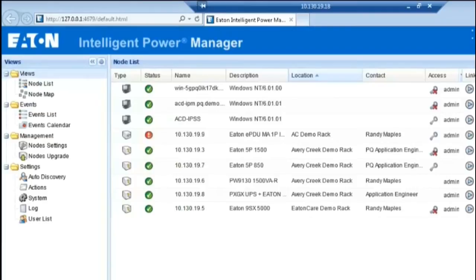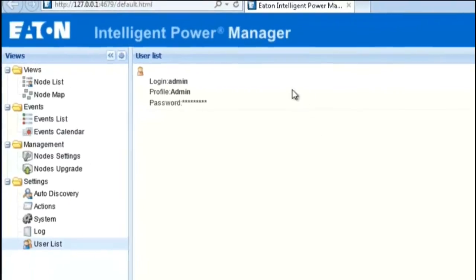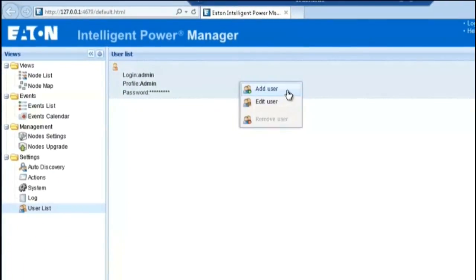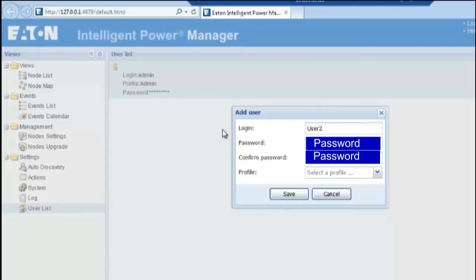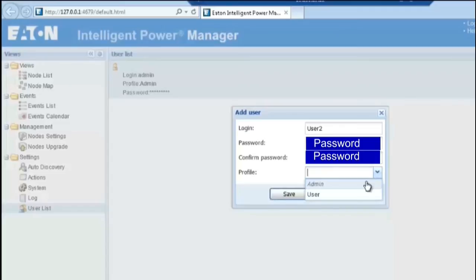Users can also be added and granted either an administrative or basic level of permissions. First, locate the Views column on the left-hand side of the interface. Next, locate the Settings folder. Then, locate the User List option. Highlight the Admin user profile found on the center screen. Right-click on the profile and select the option to Add User. Once the Add User dialog box opens, create a specific login ID for the user, then enter and confirm the desired password. Select the level of permissions granted: either Admin, which has full read-write access, or User, which has read-only access. Click Save to continue.